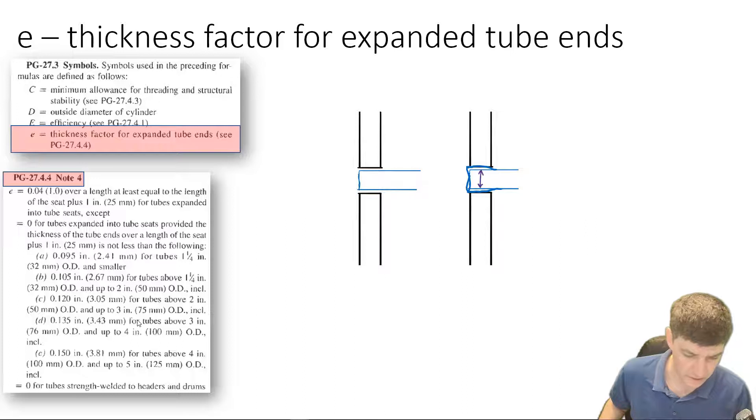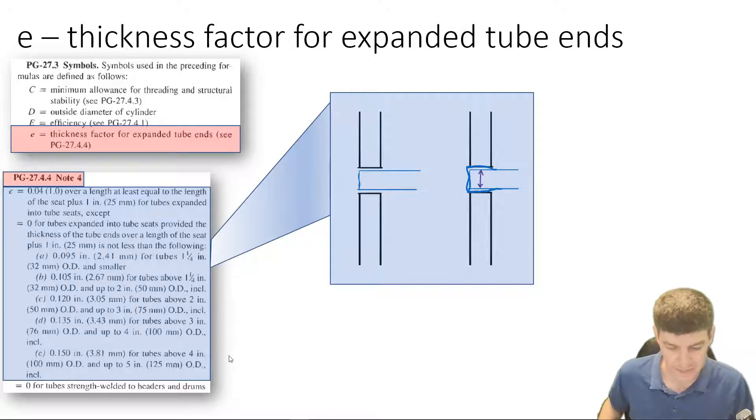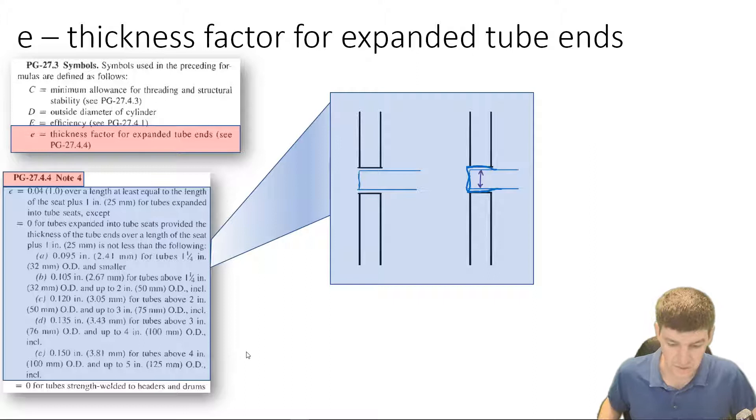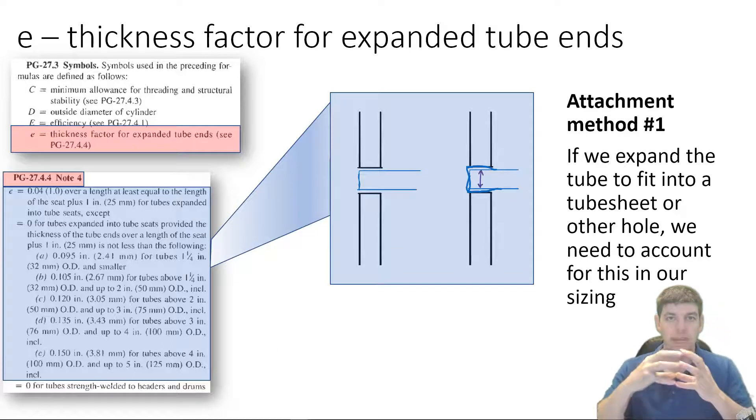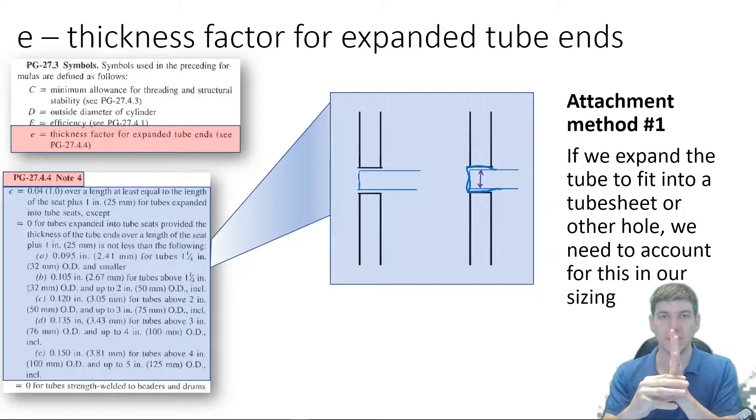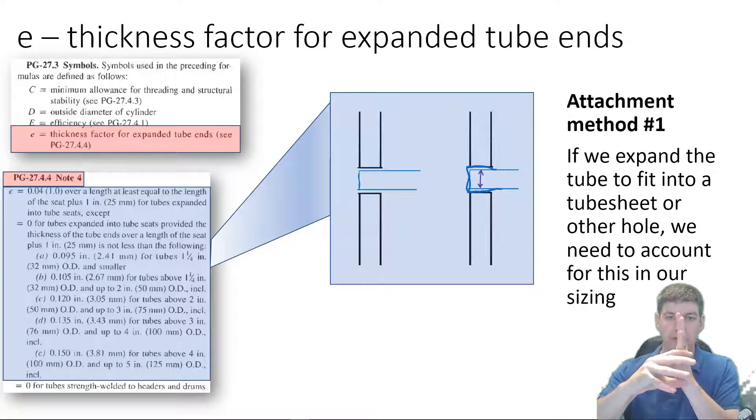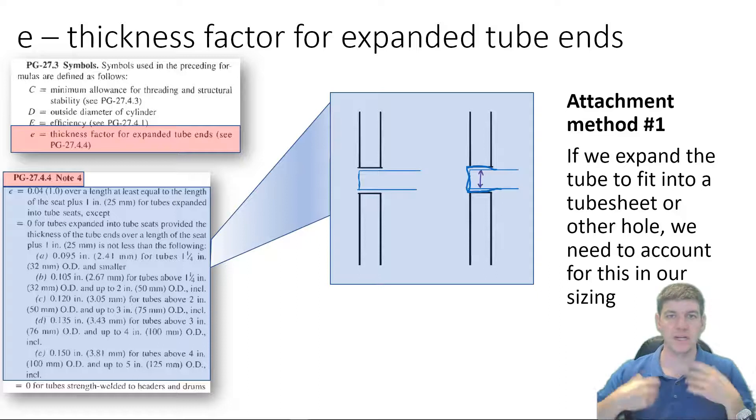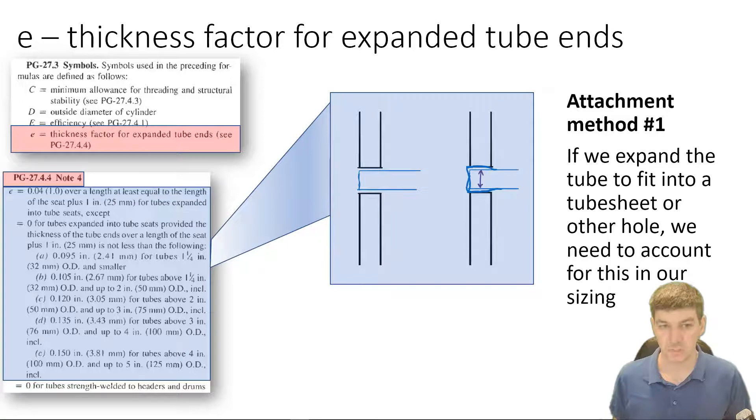Here's what this is talking about. I got a little diagram there. So, the first, I don't know, the top 90% of this is talking about one attachment method. So, if we expand a tube into a hole. So, we have, say, a tube sheet, and we stick our tube in, and then in order for it to be attached, we expand it out. So, it is tight within that hole. Well, when we expanded it, we've changed the structure of that tube. And so, this statement talks about what do we need to do if we've expanded that tube. We're probably going to have to add extra thickness to the tube to account for the weakening that we've just done by expanding it.